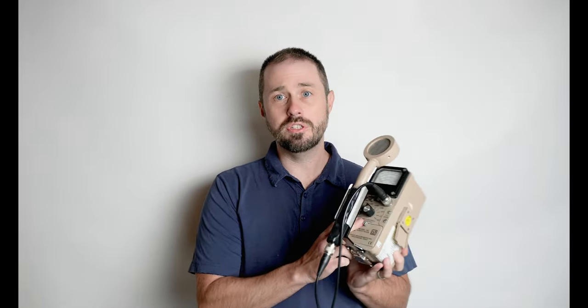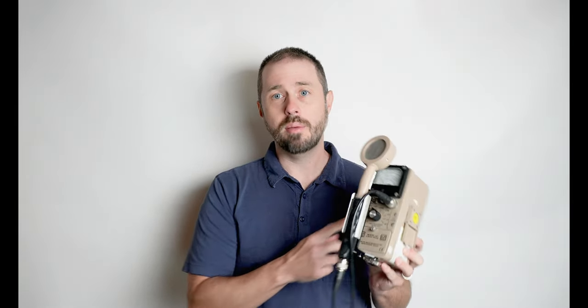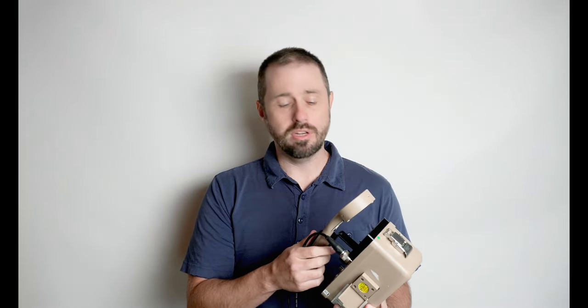And then the last thing that you want to do is check the batteries to make sure that the batteries are operating within the battery test range.